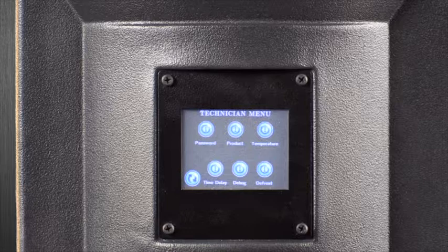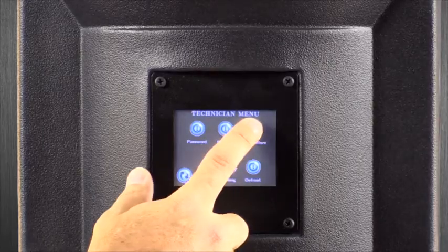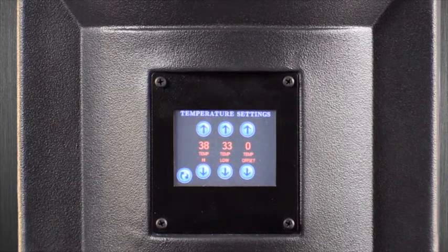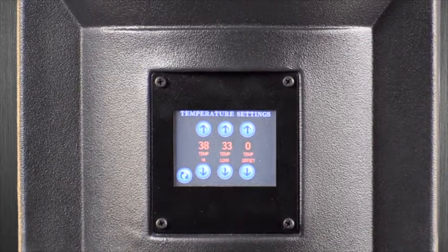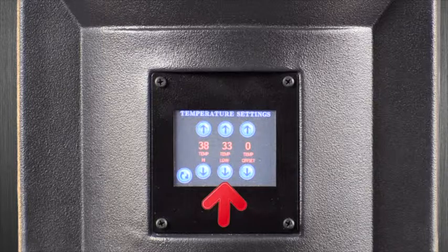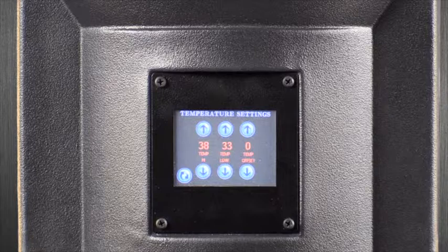Temperature. Once you have returned back to the main technician menu by hitting the back button located on the lower left, we will be selecting the temperature button located on the top right of the touchscreen. Once selected, you will see 3 settings options: temp high, temp low, temp offset. The settings that should be displayed at all times are temp high at 38 degrees Fahrenheit, temp low at 33 degrees Fahrenheit, and temp offset set at 0.